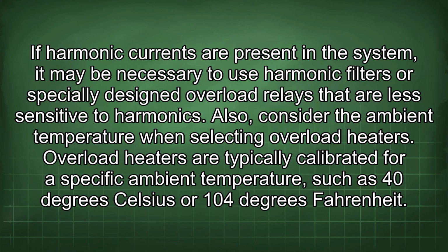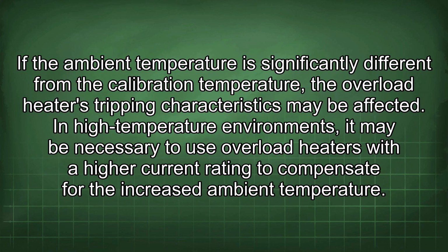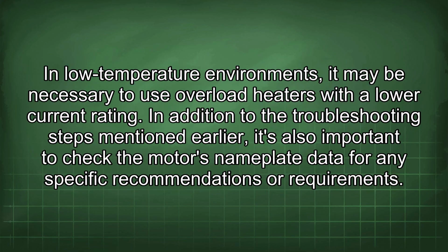Also, consider the ambient temperature when selecting overload heaters. Overload heaters are typically calibrated for a specific ambient temperature, such as 40 degrees Celsius or 104 degrees Fahrenheit. If the ambient temperature is significantly different from the calibration temperature, the overload heater's tripping characteristics may be affected. In high-temperature environments, it may be necessary to use overload heaters with a higher current rating to compensate for the increased ambient temperature. In low-temperature environments, it may be necessary to use overload heaters with a lower current rating.